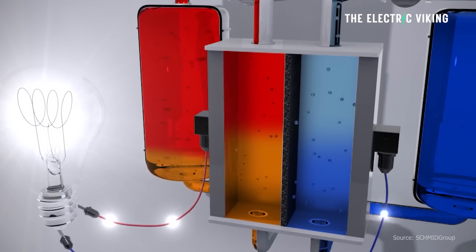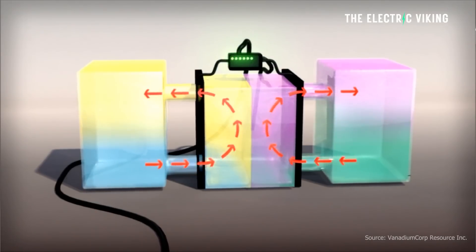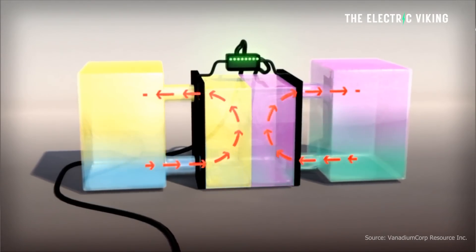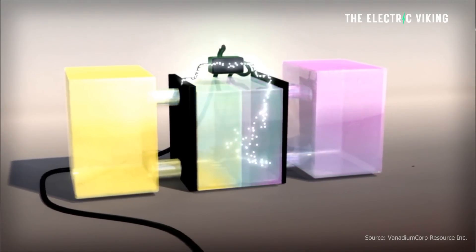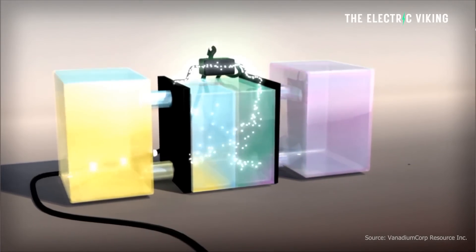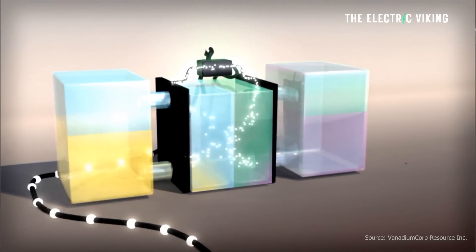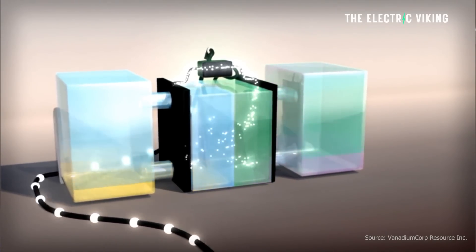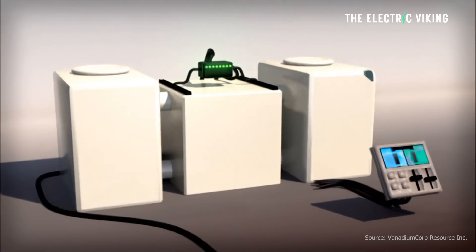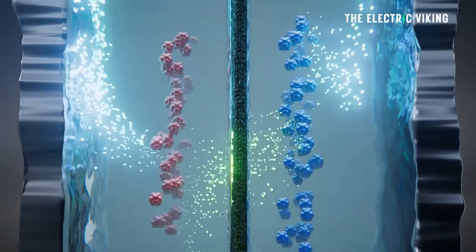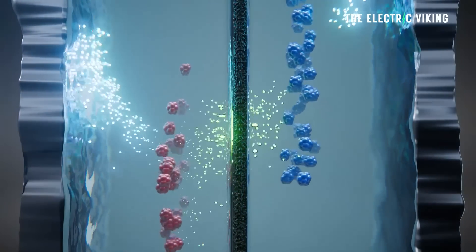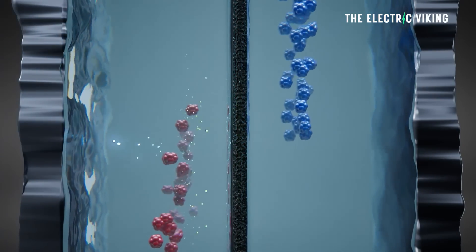The key components to a flow battery include two electrolyte tanks, one for positive electrolyte and the other for negative electrolyte, a pump to circulate the electrolytes, and an electrochemical cell where the reactions occur. The flow battery operates by pumping the electrolytes from the storage tanks into the cell where the chemical reactions generate electrical energy. The flow of the electrolytes can be controlled to adjust the power output and storage capacity of the battery.